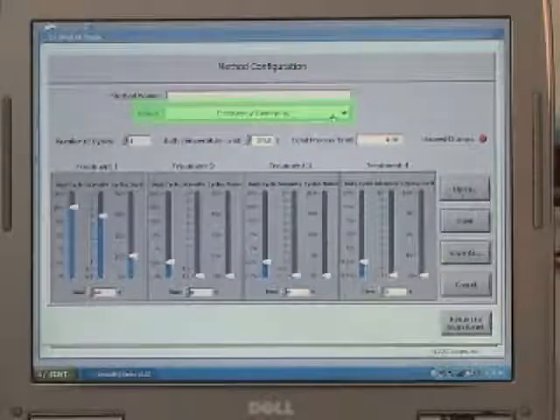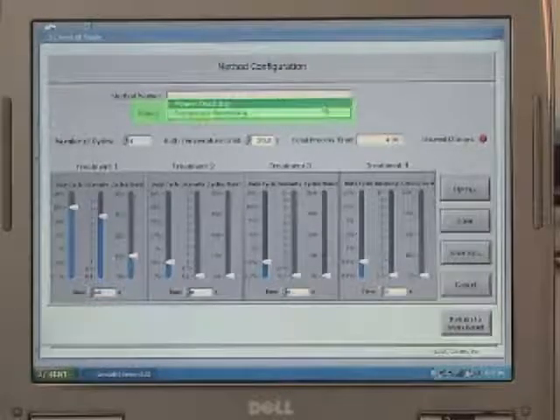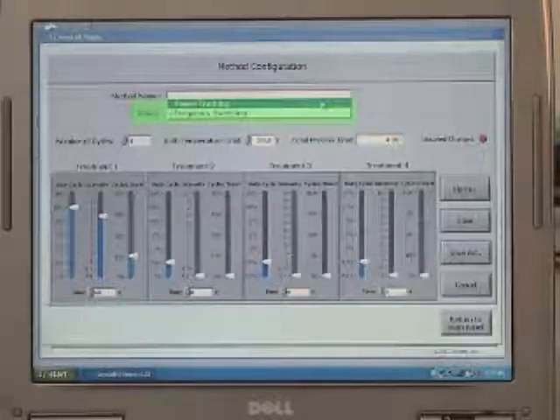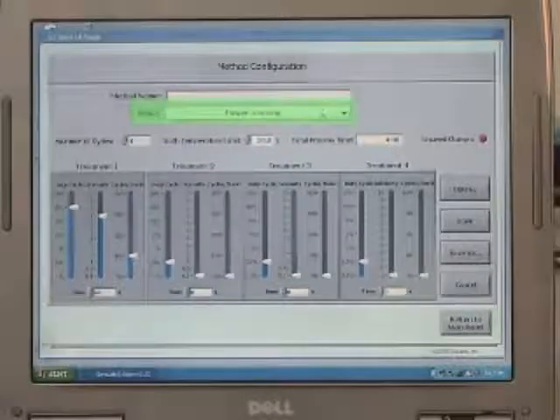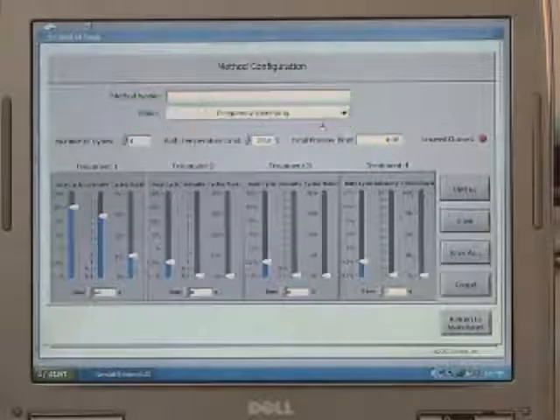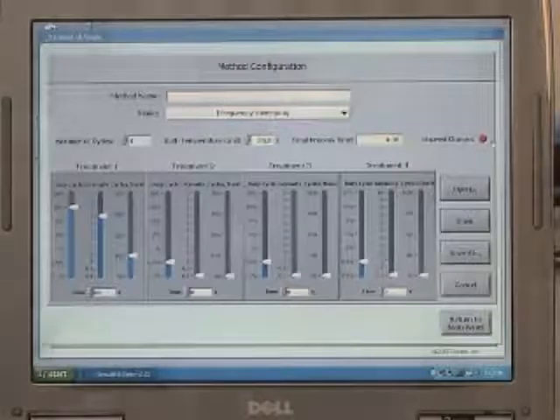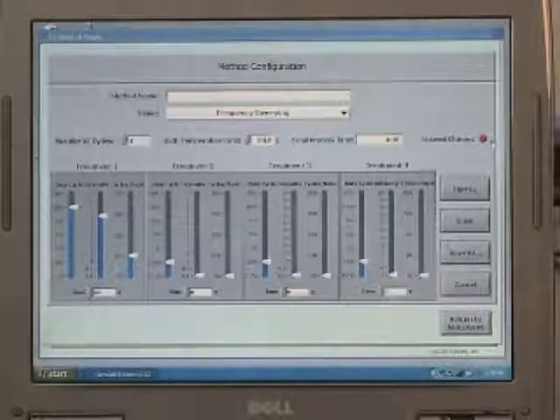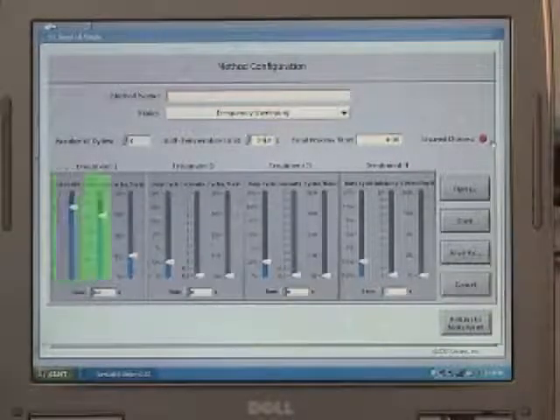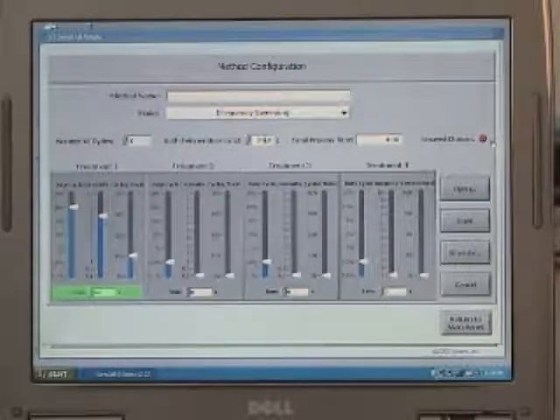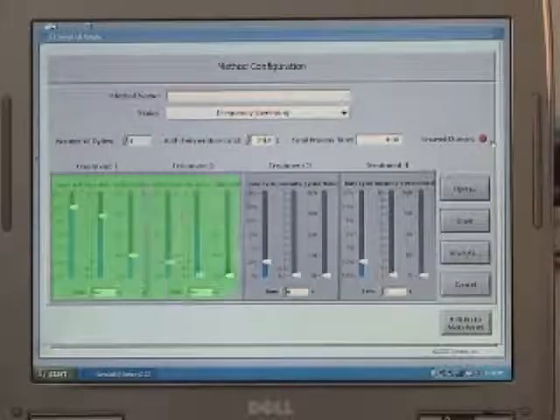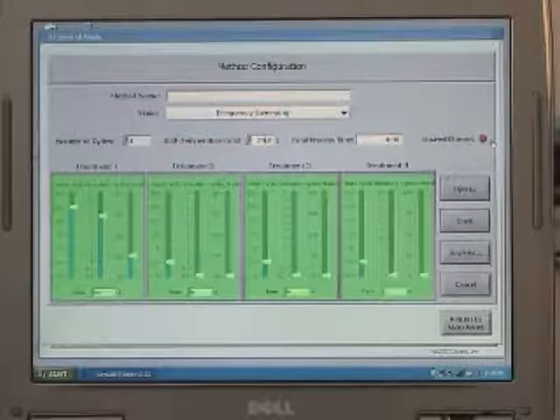Click on the mode name to select Frequency Sweeping or Power Tracking. Frequency Sweeping is the default mode. Refer to the manual for information on selecting the appropriate mode. Now, on to the treatment panels. The 4 operating parameters for each treatment are duty cycle, intensity, cycles per burst, and time. Up to 4 different treatments can be grouped together in a single method.